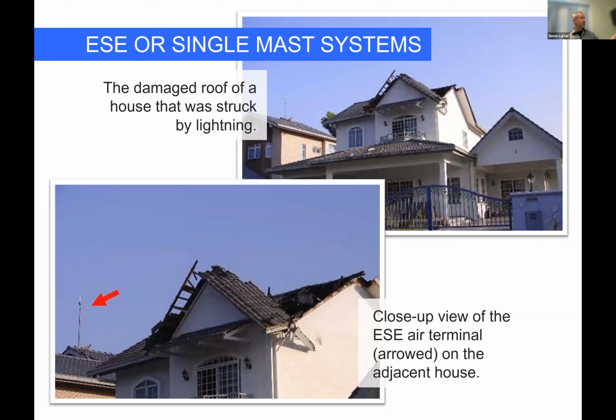But I looked just to the left from the ESE device that's supposed to protect this big wide area, and at the end of the parapet over there, the only reason chunks of stone hadn't been blasted off and fallen 150, 200 meters to the street below is because they'd recently put a waterproof coating around it, fiberglass reinforced, and the fiberglass was actually holding the stone together, but it was falling apart because the lightning hit the stone at the edge. Wasn't supposed to, because this mast system was supposed to protect the whole damn building, except it didn't. That's why I don't recommend these things, and you won't see very many because there's no code support in Canada for them.